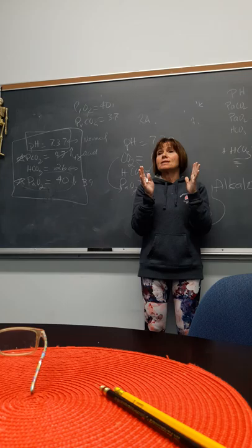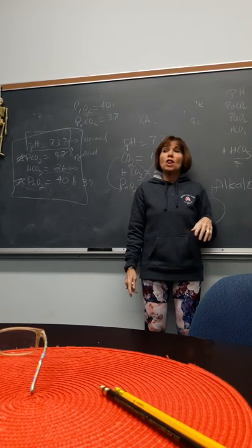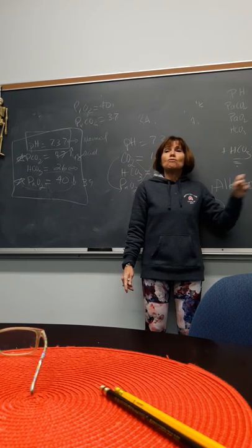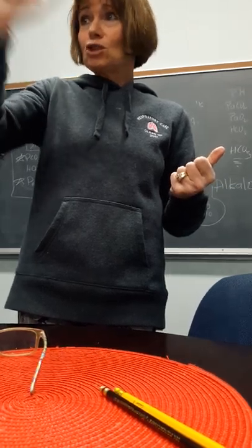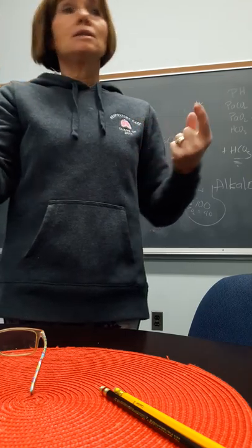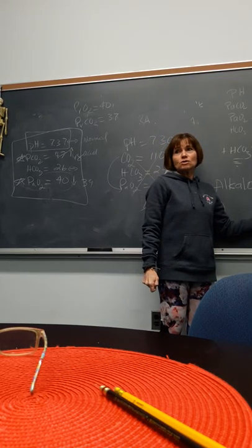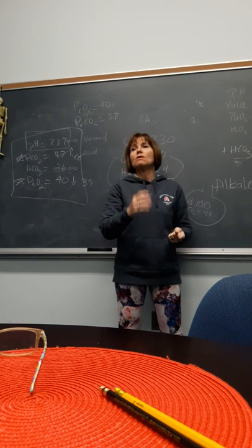Now, if we fix something on the machine, we have to run all three, and all three have to come in. If you run and it doesn't come in the first time, it might be because of the gas in that vial. If you don't shake it well, your QC might be off. So if you watch, she shook it really well and then ran the blood gas. If the first one doesn't come in, try a new vial, shake it. If it doesn't come in the second time, your machine is not in service, because this QC is saying these are known values and you're not getting those known values. Take your machine out and figure out what the problem is.